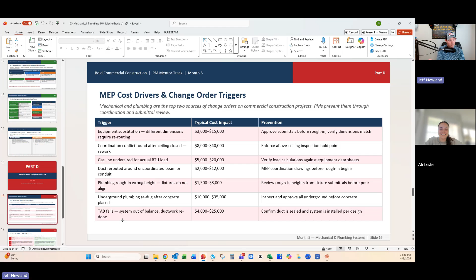Plumbing's at the wrong height depending on the fixtures. The most common thing here would be location, not necessarily height, like a toilet. So plumbing height being wrong, if it was a urinal and they didn't plumb the water high enough, or plumbed it too low, that's obviously a problem. Underground plumbing redug, that's most commonly a floor drain or a commode drain where we've poured concrete and now have to chip it out to move the thing. And then TAB fails. Some reasons your TAB would fail: not insulated properly, they didn't pookie your ductwork at all, or you've got a leak somewhere, that's why your TAB would fail.